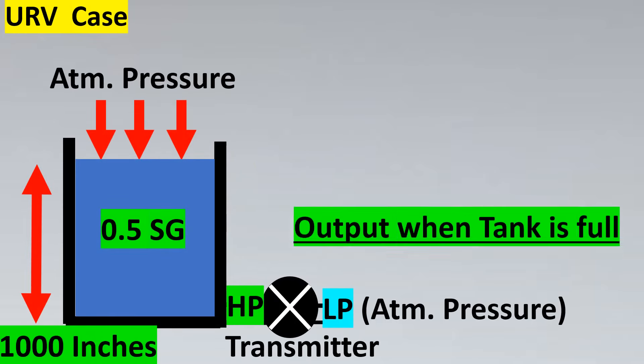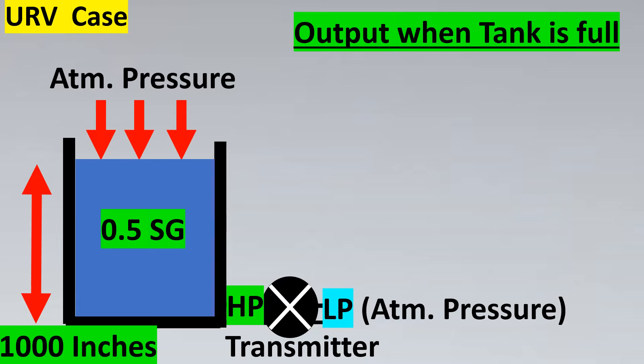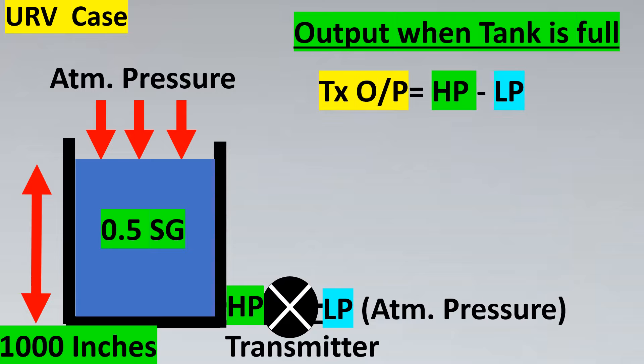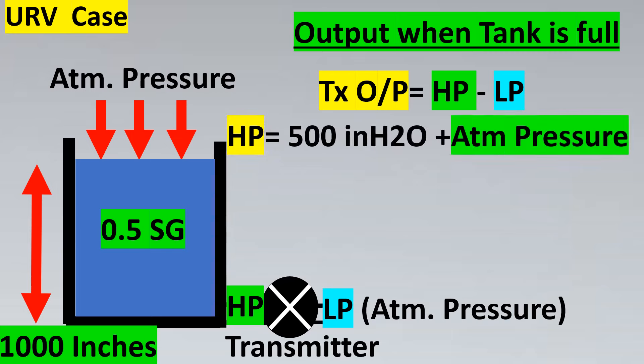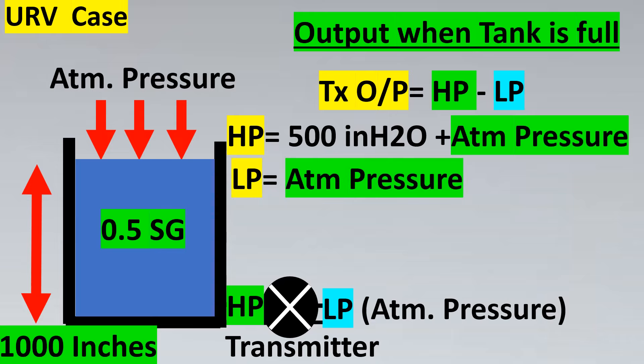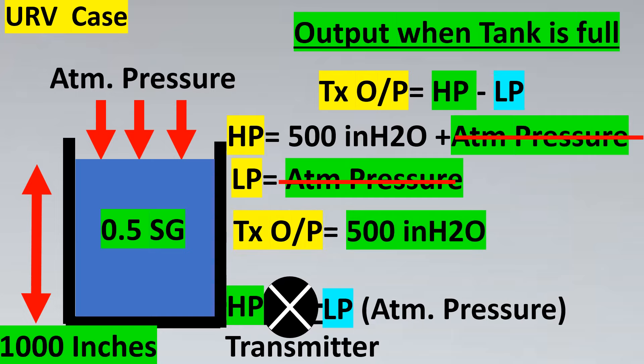To confirm: the transmitter output when the tank is full is HP minus LP. HP was 500 inches of H2O plus atmospheric pressure; LP was atmospheric pressure. The atmospheric pressure cancels, so the transmitter output is 500 inches of H2O when the tank is full.